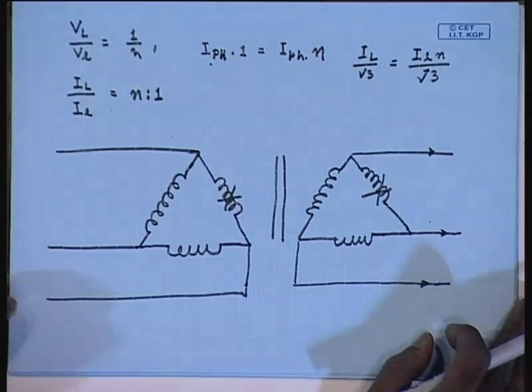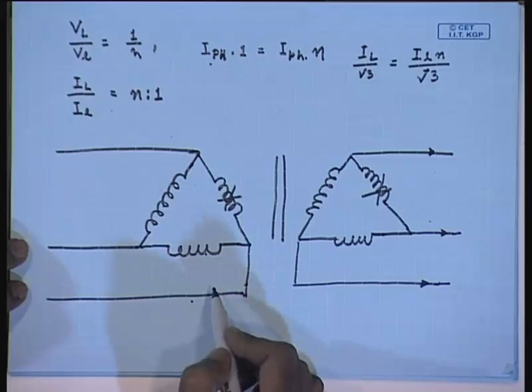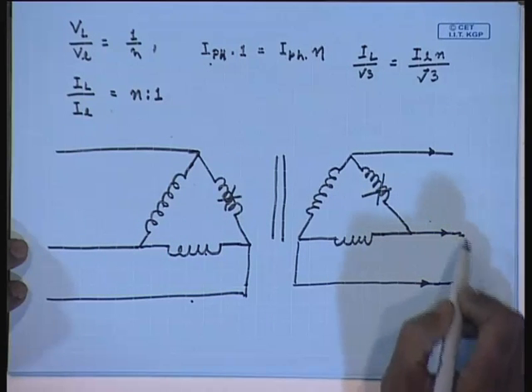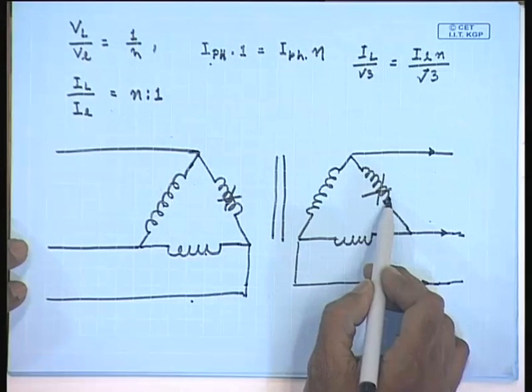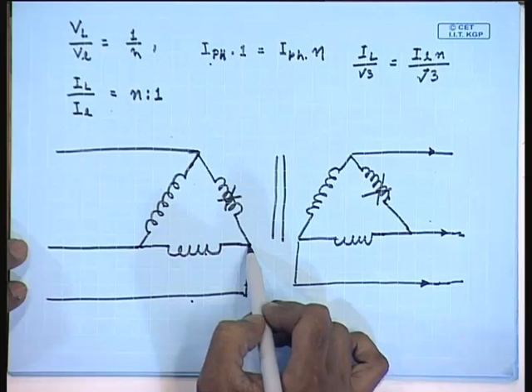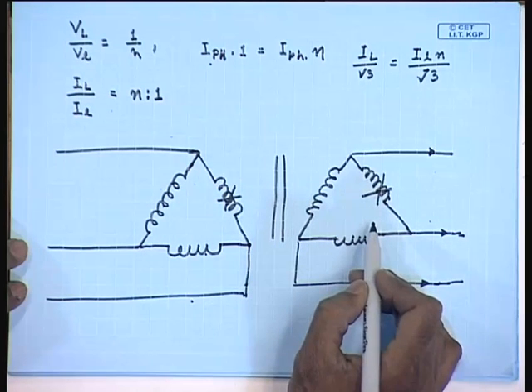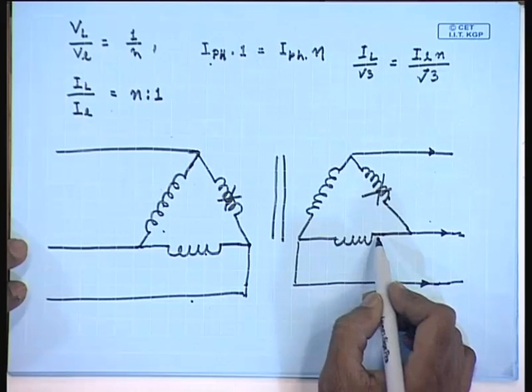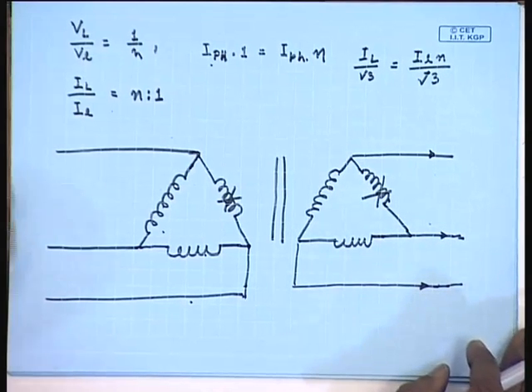Then the remaining transformers can still continue to supply some amount of load. When you remove these windings, you get the structure known as open delta or V connected transformers. A V connected transformer can continue to supply the load. That is one advantage of using 3 single phase transformers separately to form a 3 phase transformer rather than using a 3 phase transformer as a single unit. Sometimes this is important. Let us see exactly how much kVA or power can be supplied with this open delta connected transformer or V connected transformer through an example.